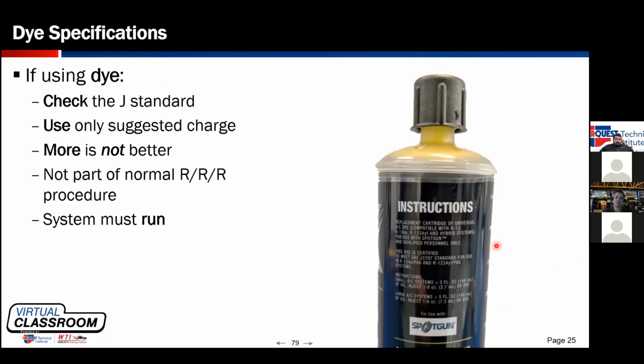This particular bottle of dye, they consider a small AC system, a system with less than 5 ounces of oil capacity, which is most of our systems. They want 1/8 of an ounce of dye. But it shouldn't be part of your standard procedure to just add dye to the system. You should only be adding dye if there is no dye. One dose of dye for the system is enough. In order for dye to show a leak, the system has to run. We have to circulate that refrigerant and oil in order to find that leak.